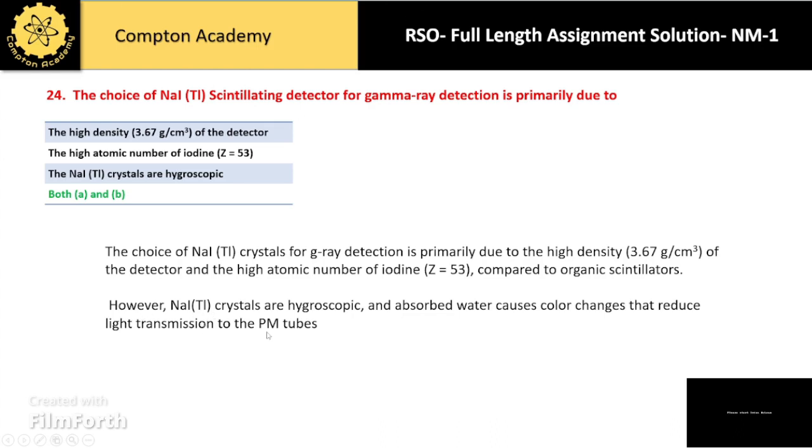And the sodium iodide hygroscopic nature, it will be affected by the moisture or water and then reduce the light emission efficiency of this sodium iodide detector.